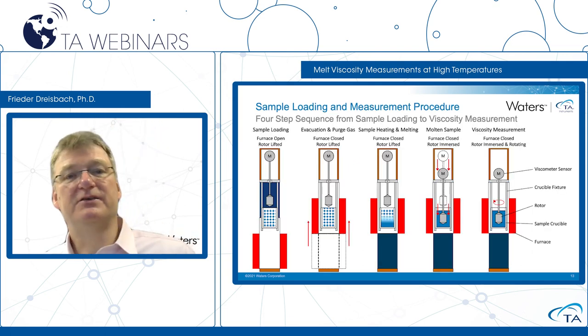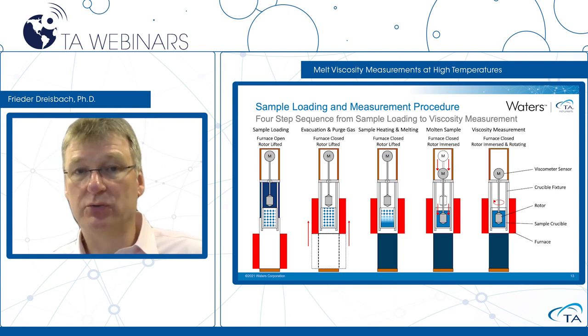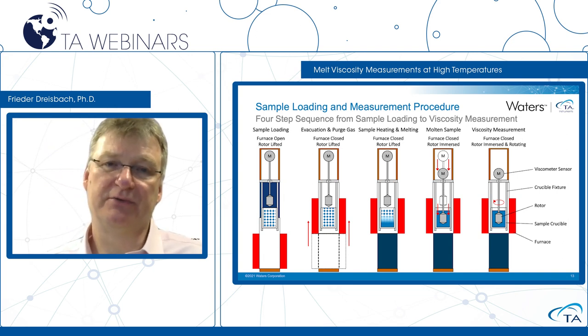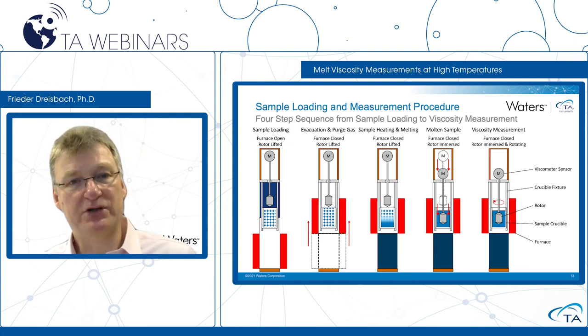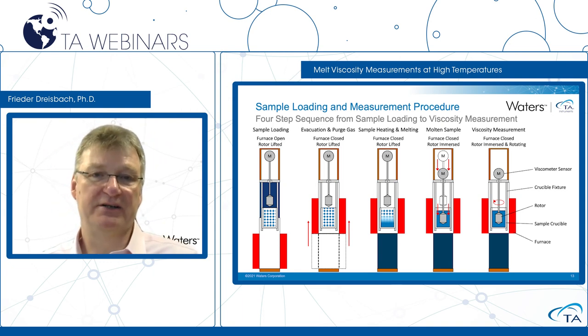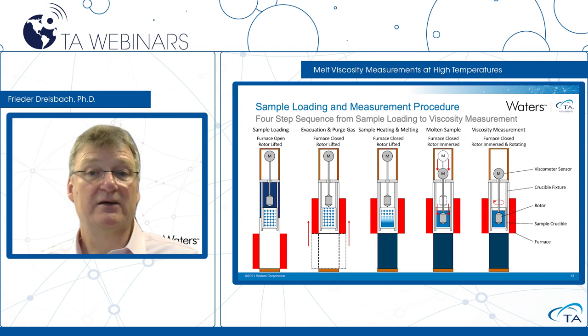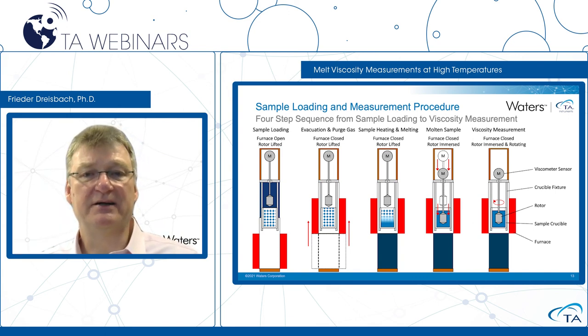This slide shows the measuring principle. Starting from the left: the sample crucible with sample is loaded as shown in the video. Then the furnace is lifted electrically. From this point, we can evacuate, remove the air, and purge the inner volume to provide an oxygen-free atmosphere before heating. Then we start heating the sample, the sample melts, the rotor is lowered from the top into the molten sample, and finally the measurement starts by controlling rotational speed and measuring the torque required.